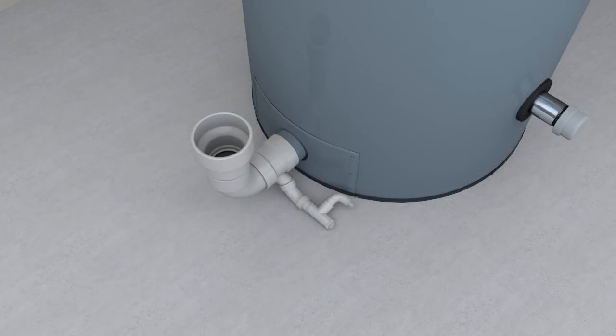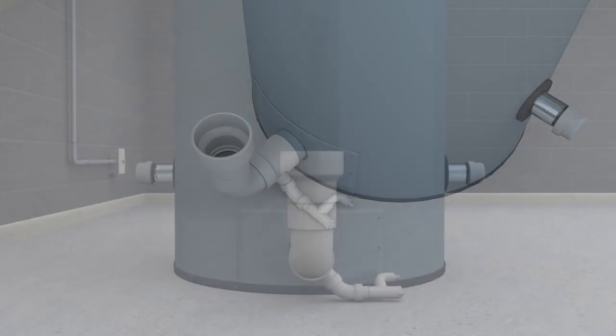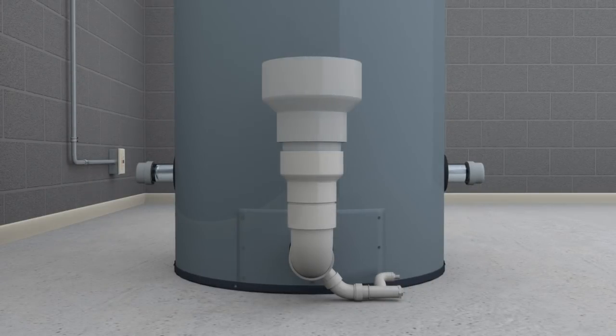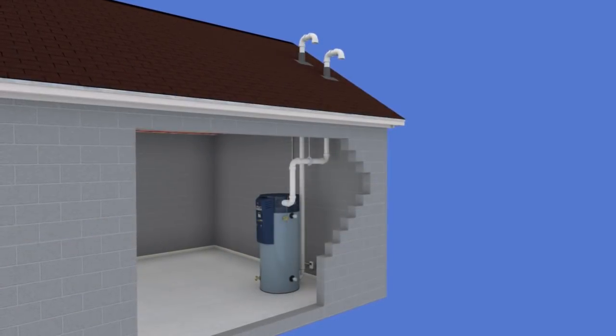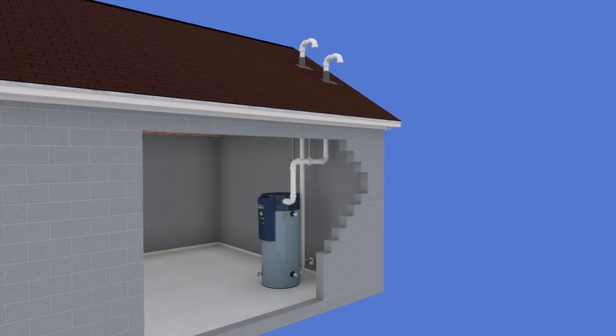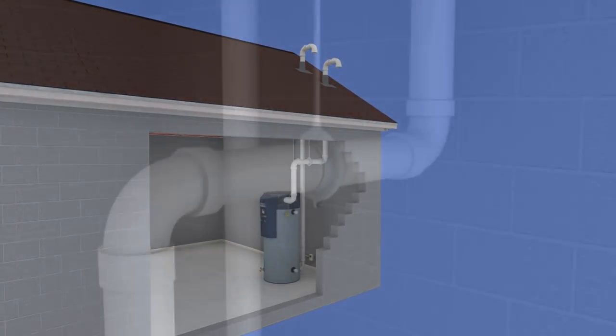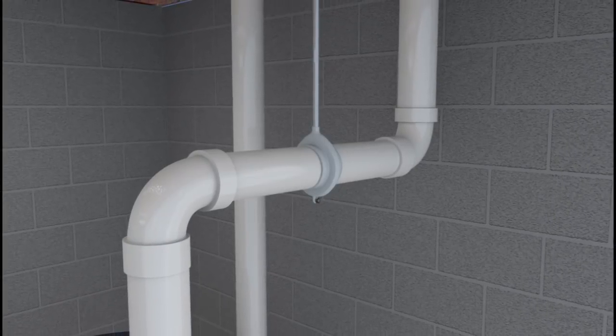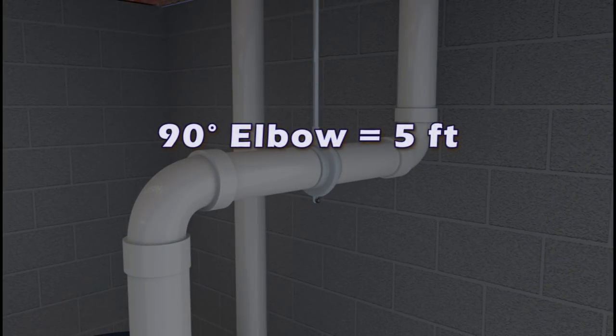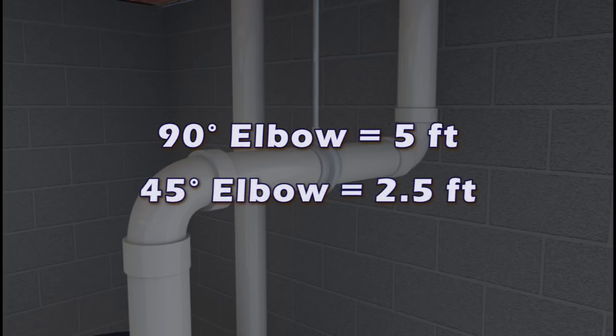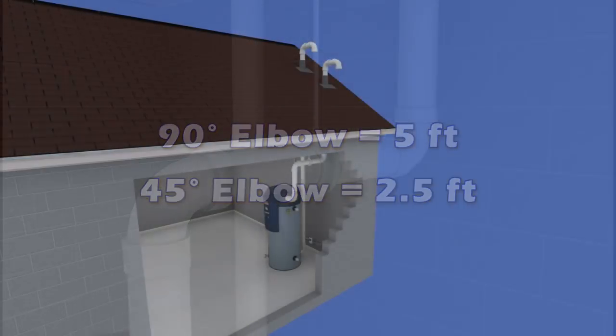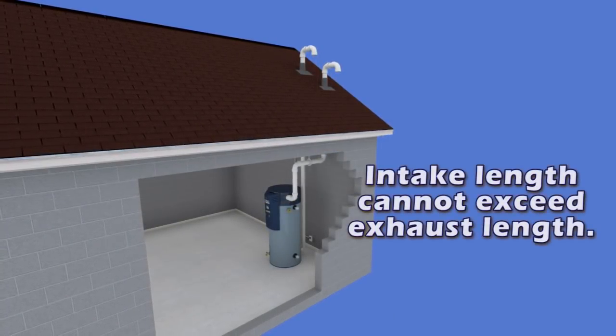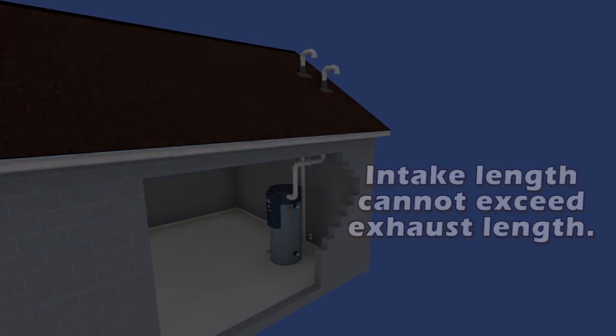Intake and exhaust vent pipe and fittings can be made in either 4-inch or 6-inch PVC or CPVC. Do not use unequal vent sizes except to increase from 4-inch to 6-inch piping at the water heater. The location of the water heater should be chosen so as to keep vent lengths and the number of fittings to a minimum. Each fitting has an equivalent straight pipe length. A 90-degree sweep bend elbow is the equivalent of 5 feet of straight pipe, and a 45-degree sweep bend elbow is the equivalent of 2.5 feet of straight pipe. The equivalent intake length cannot exceed equivalent exhaust length.